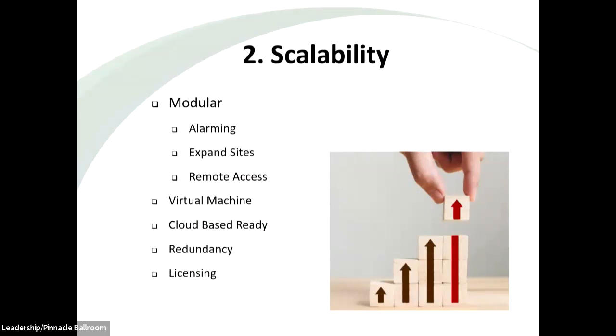And then licensing. Typically, most SCADA systems are purchased through a tag-based licensing scheme. That means you purchase a license for a number of devices that your SCADA system can communicate to. At some point, if you exceed that number of licenses, or creep up to maximizing the number of points you're communicating to - your valve, your pump, your motor - you can expand that tag license and purchase a larger license, to the point where you're now running 10,000 points, 20,000 points. We have seen SCADA systems with 1 million points. That's huge, not in the municipal business, but the idea behind scalability is to purchase your licenses and grow them as you need to.